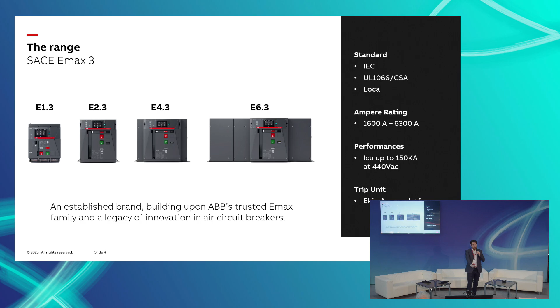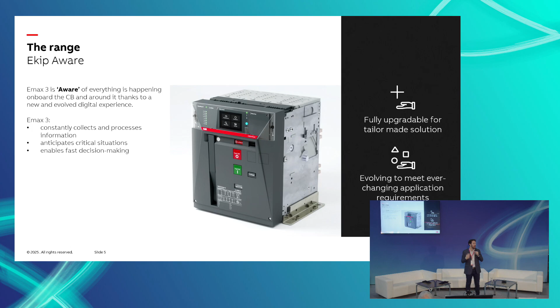So what has really changed is the trip unit. You can see here the trip unit is the intelligent part of the breaker. As the name suggests, it is aware of what is happening inside and also outside the circuit breaker. We have added a lot of new sensors and new technology in the same space as before, in order to be aware of the breaker itself and also what is happening in the switchgear asset.